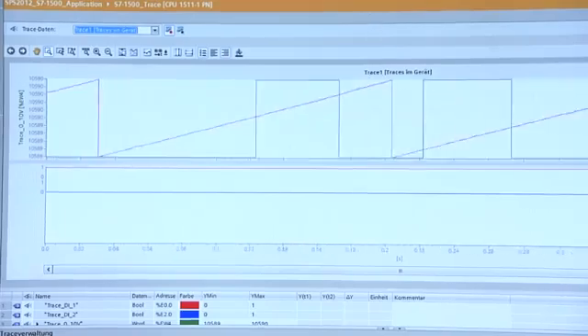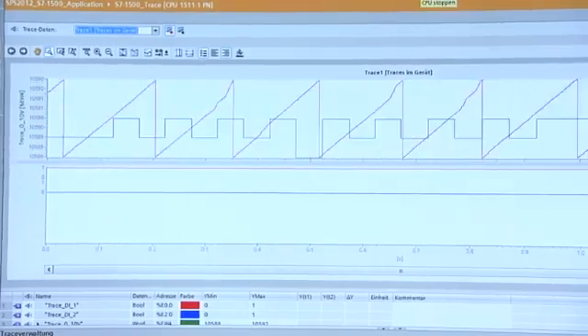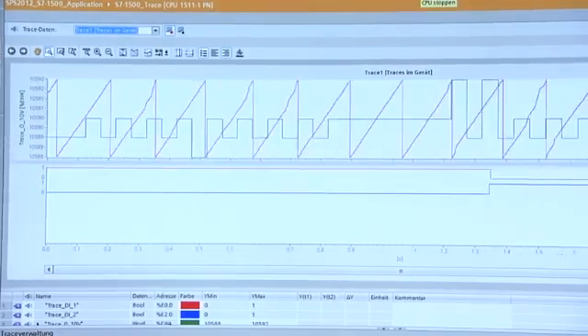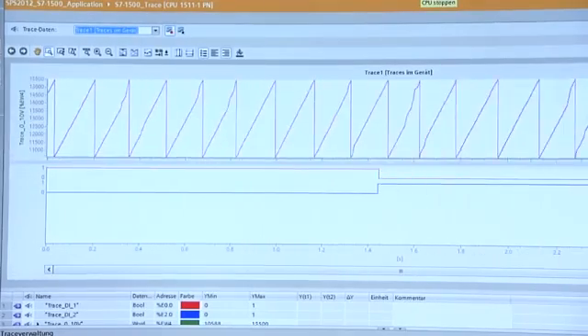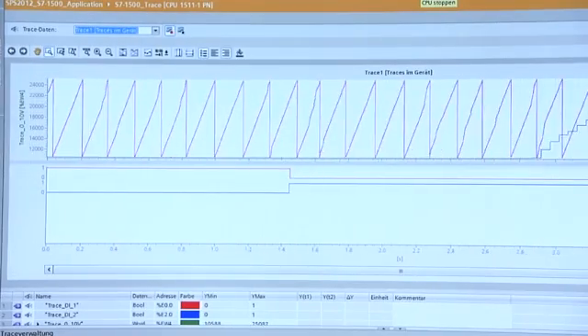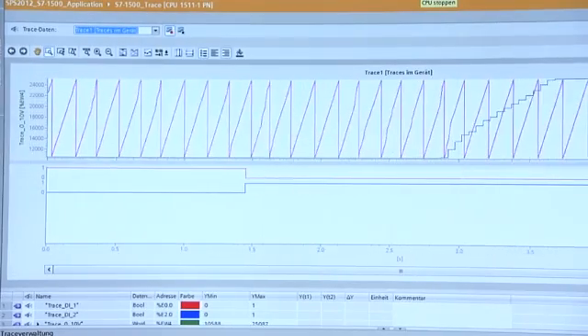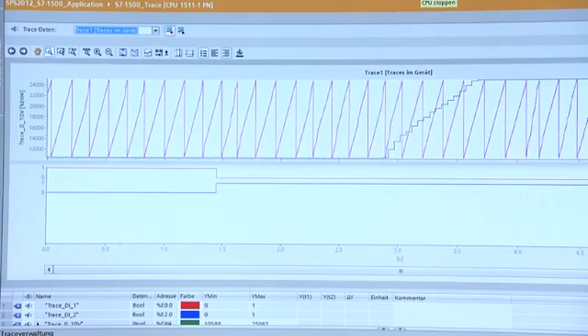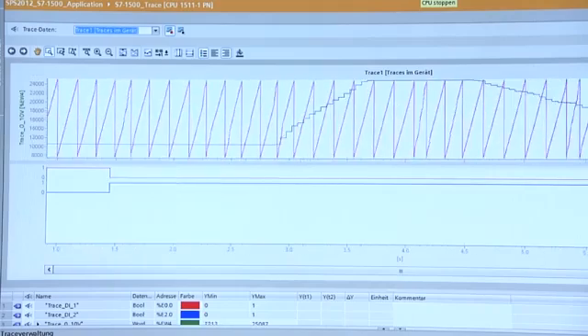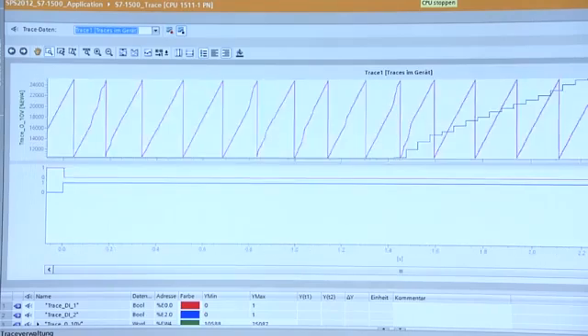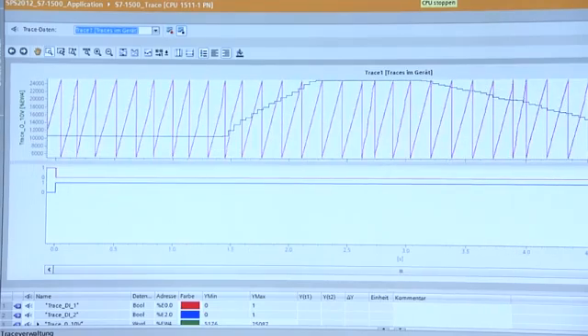You can use the new trace function with all CPU variables, tags, and even I/O signals. This tool can help you optimize drive applications, as well as help you for diagnostics of sporadic issues while troubleshooting and commissioning. Four traces with 16 signals each can be used in parallel for analysis in a single controller.